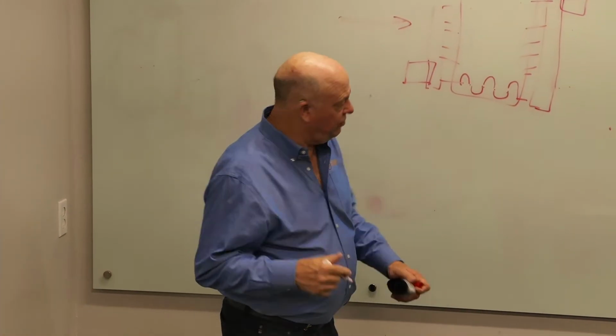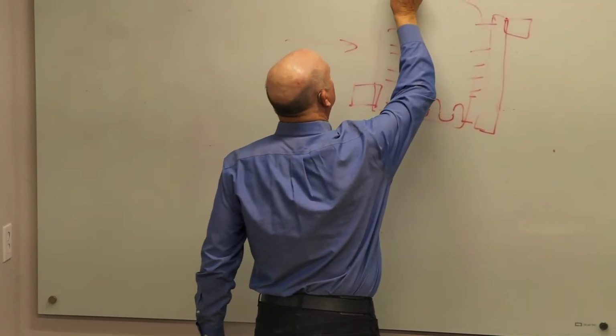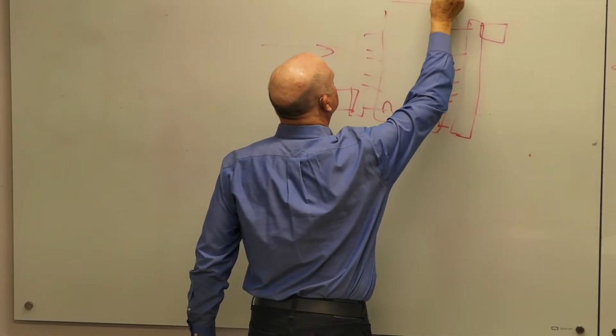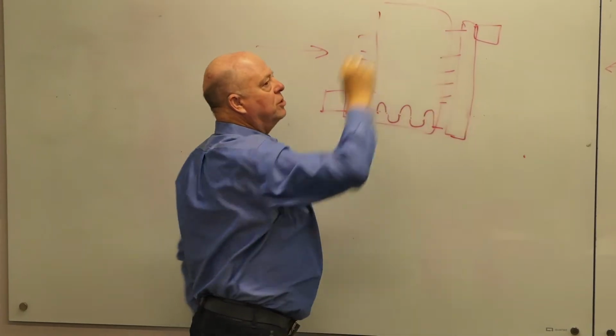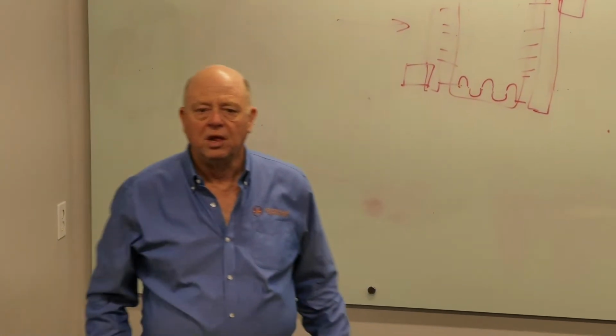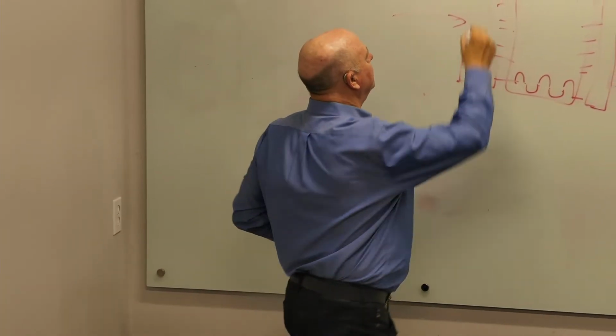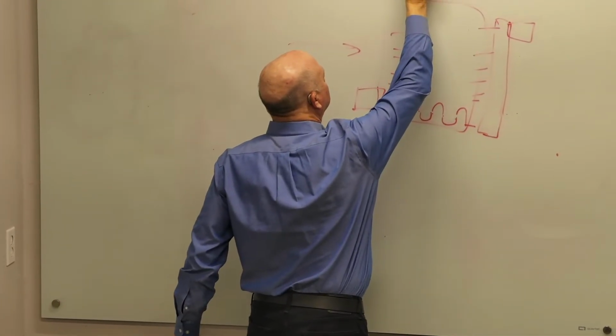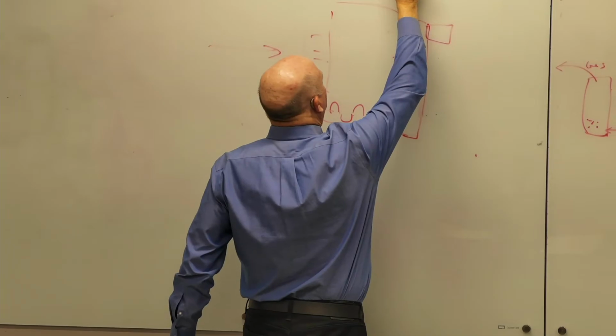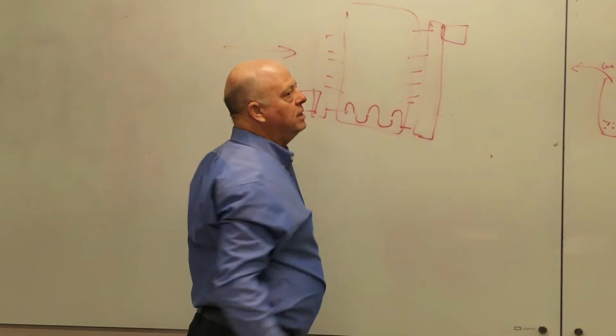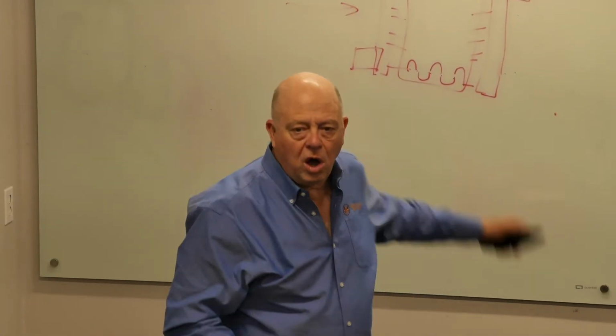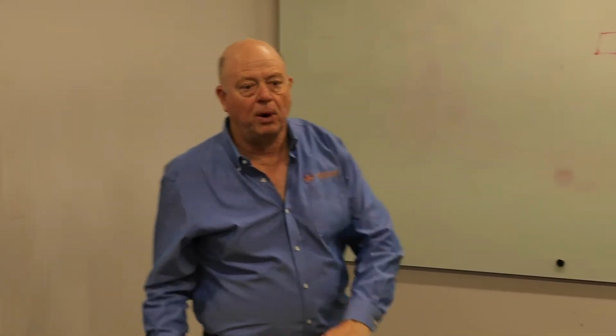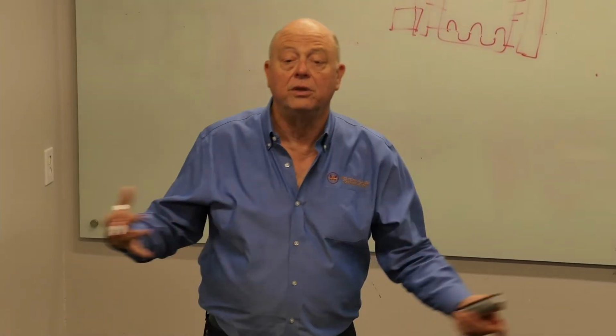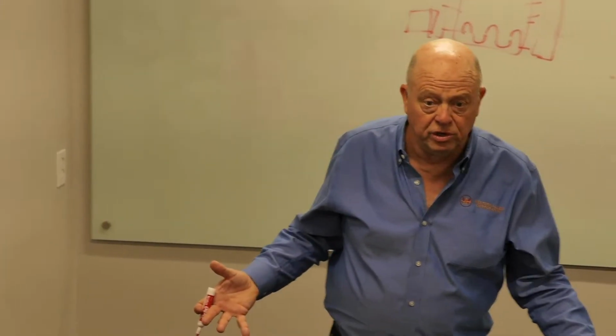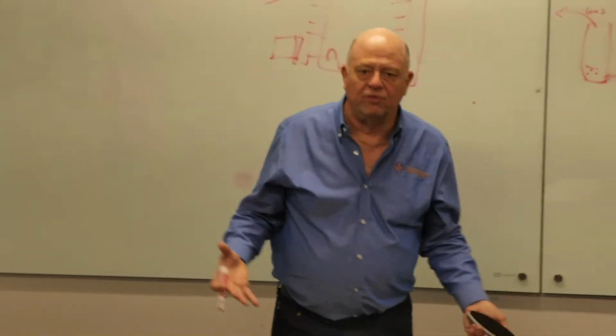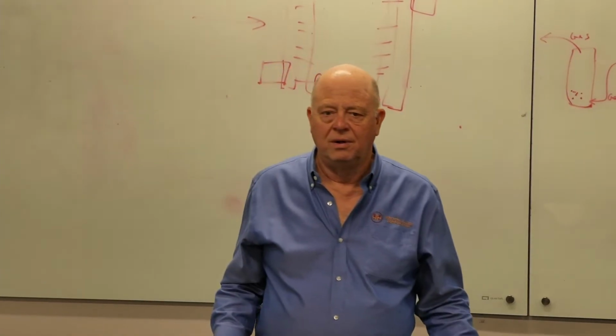So, Carrier did research on this. The typical cooling coil in air conditioning over the years has been 4, 6, or 8 rows. If you pipe it parallel instead of counterflow for a 4-row, you lose 20%. Here you lose 15, here you lose about 17. Parallel flow costs you that much as opposed to counterflow in your capacity, in your heat exchange. So getting it right for counterflow is a huge deal.